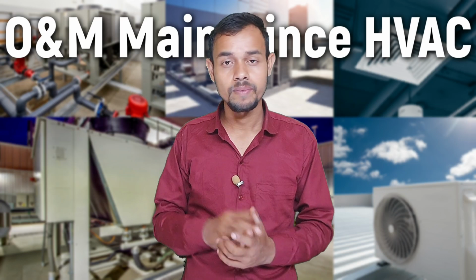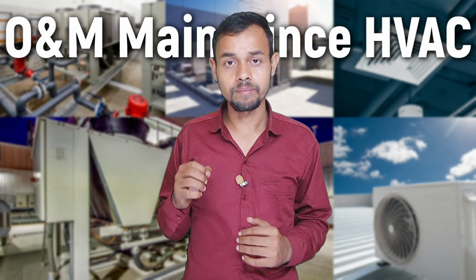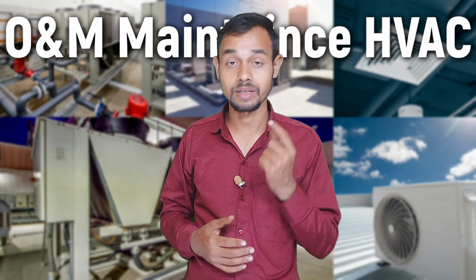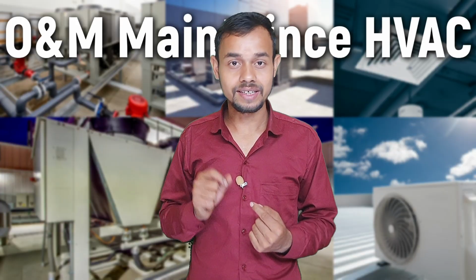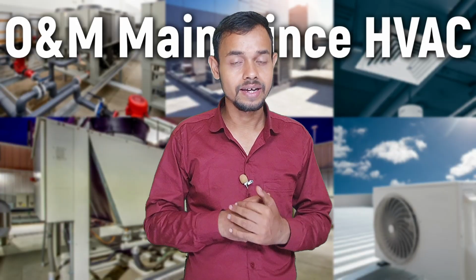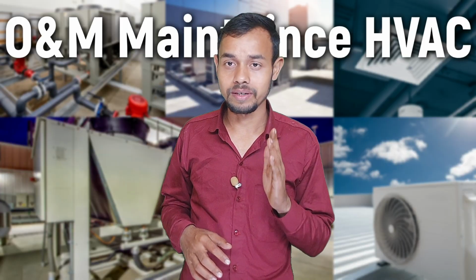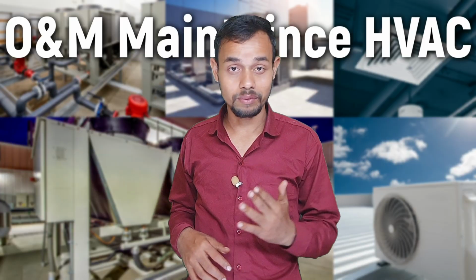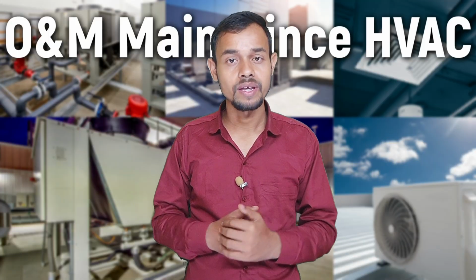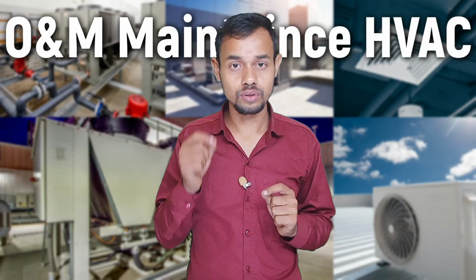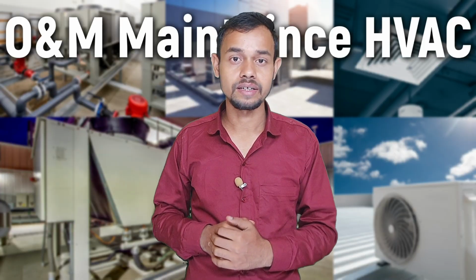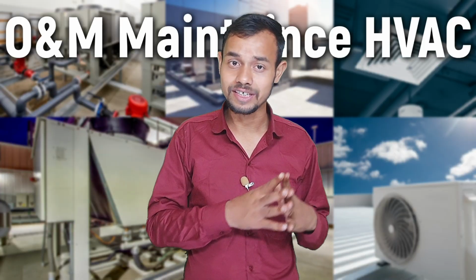For example, in preventive maintenance you do filter cleaning and coil cleaning, belt tensioning, lubrication, and chemical water treatment in the chiller line and cooling tower line, vibration testing of motors and AHUs, data logging, sensor calibration, and imagine if AHU filters get choked.